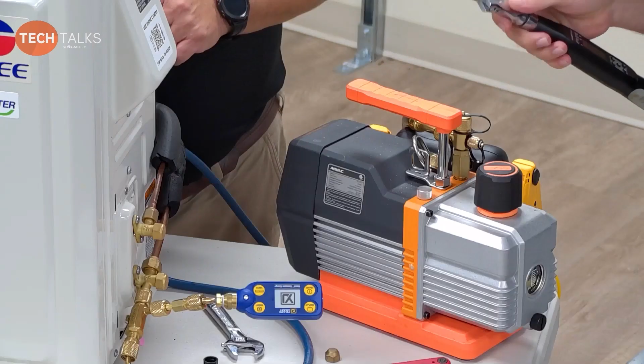I was using an adjustable wrench about this size, and when I tightened that quarter-inch one down, then put nitrogen pressure on it to check for leaks, it blew the quarter-inch out. So I made it again, tightened it down, and did it again. What I ended up doing is getting a smaller pocket adjustable wrench to get it up and going, and I had to use the leak detector and tighten it some more to get it to stop. I wasn't over-tightening it - actually I was over-tightening that flare, and I was snapping the flare face off of the copper.